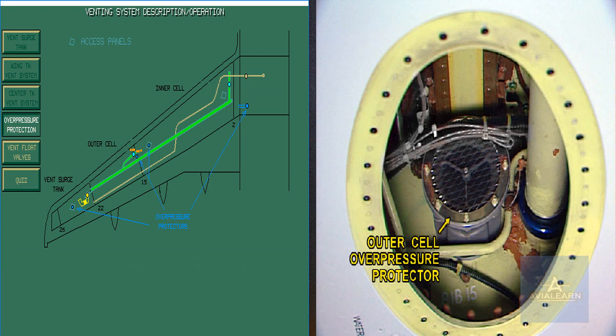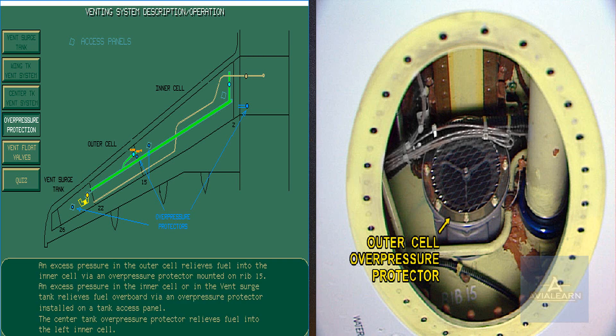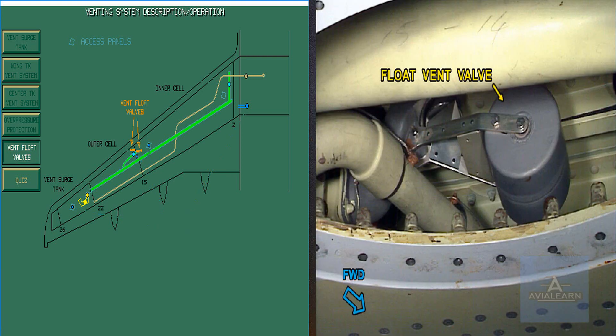Over-pressure protectors are installed in the system to relieve pressure in the tanks that might occur through vent blockage or a pressure refueling gallery failure. Two vent float valves prevent fuel from passing into the vent lines during aircraft bank maneuvers.